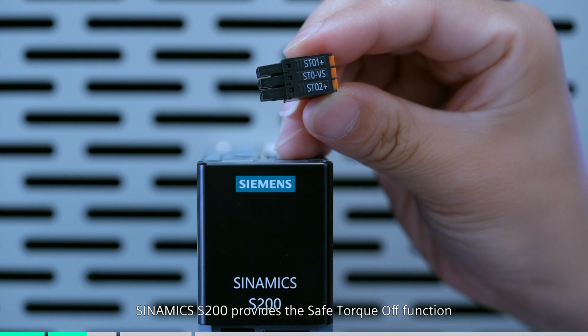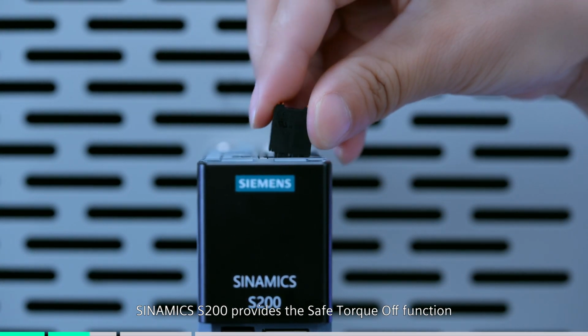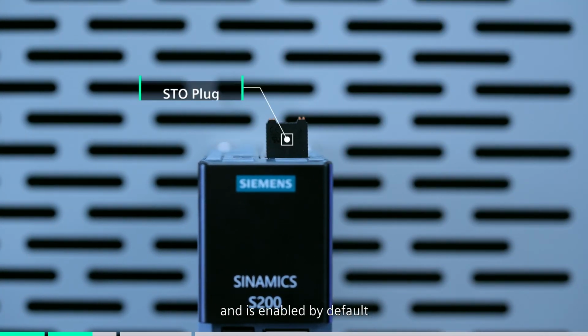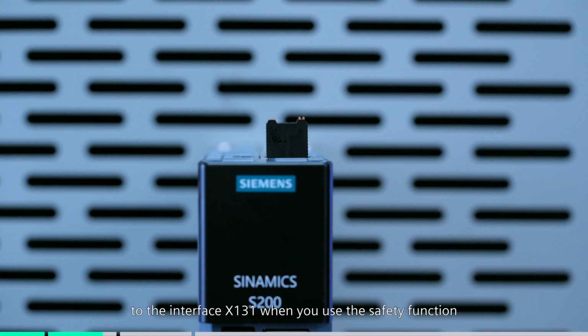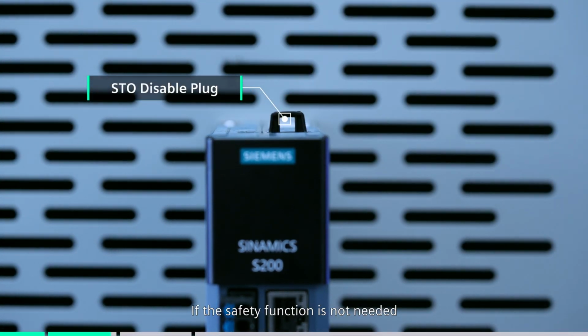SINAMICS S200 provides the safe torque off function and is enabled by default. There are two STO channels for connection to external safety devices. Please assemble the STO plug to the interface X131 when you use the safety function. If the safety function is not needed, please insert the STO disable plug to the servo drive.